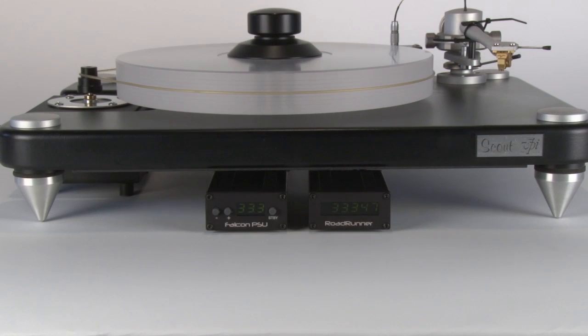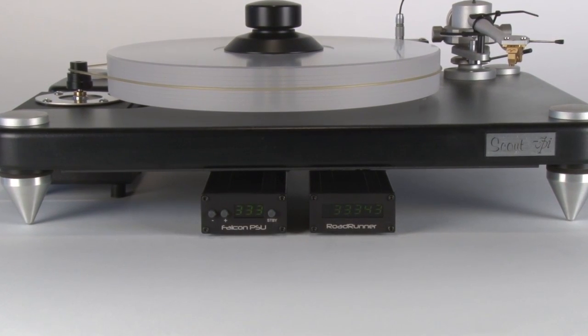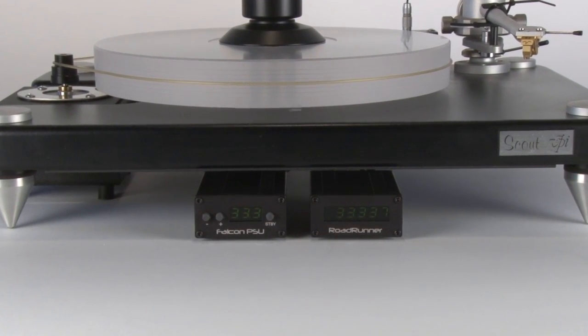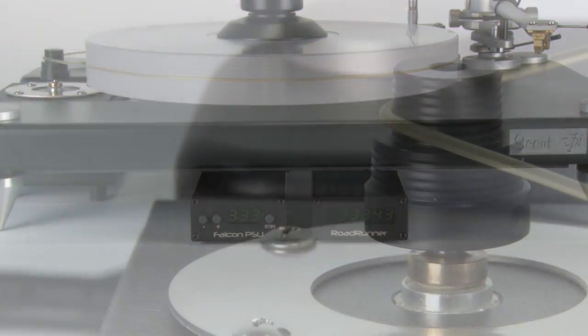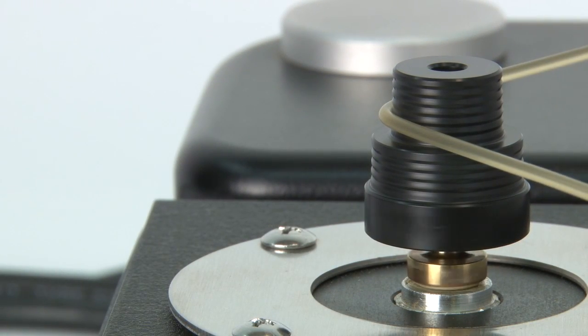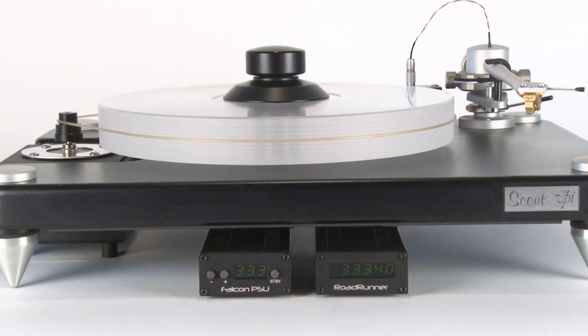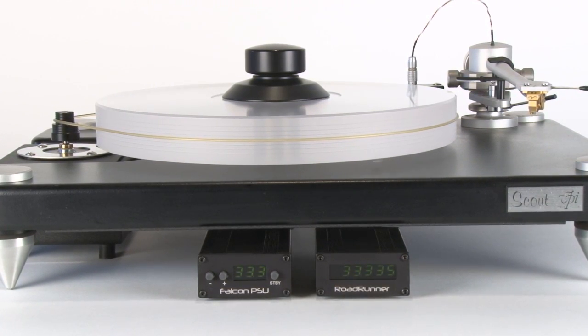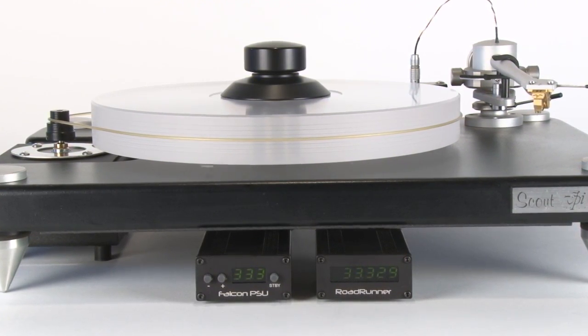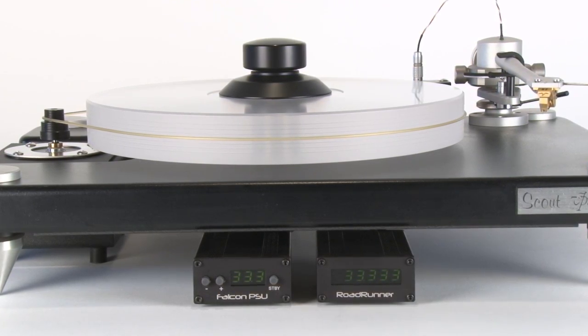Voltage output mode. The voltage output mode is used to adjust the output voltage the power supply reverts to after the platter has reached operating speed. The motor requires much more torque at startup than it does once the platter is on speed. By reducing the running voltage once the platter is moving, vibration and noise are greatly reduced. The power supply will always assert the maximum output voltage when starting or changing speeds, then revert to the programmed lower voltage after approximately 3 seconds.